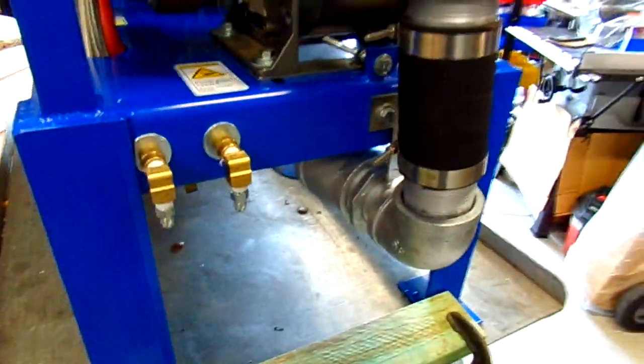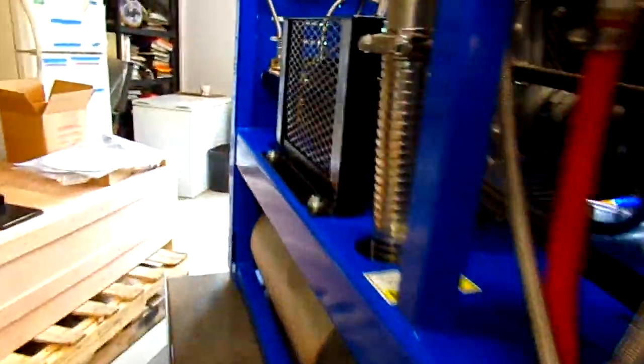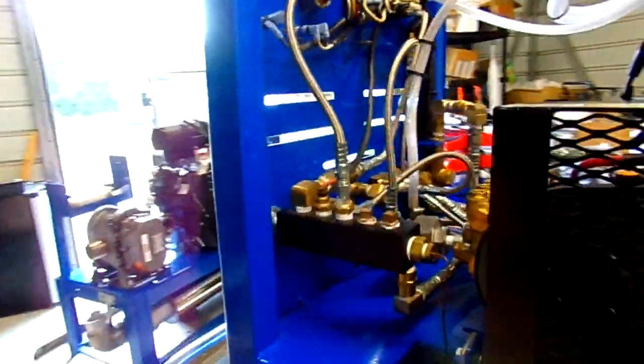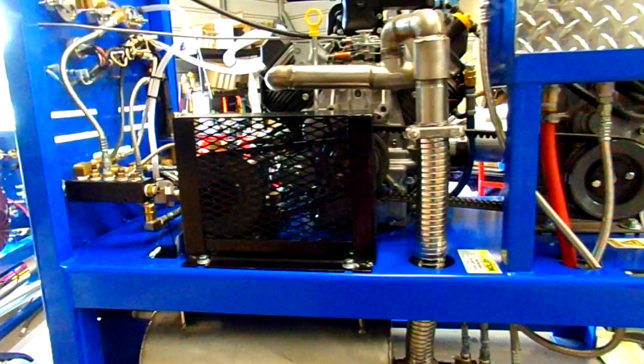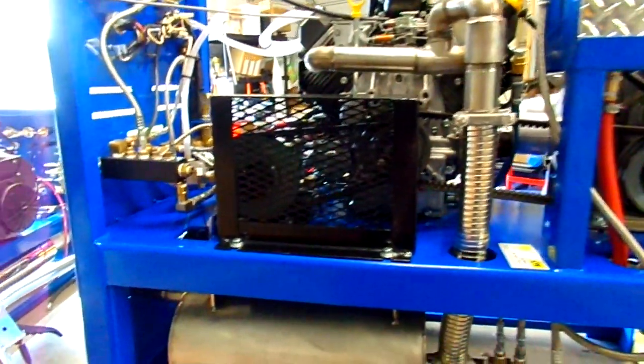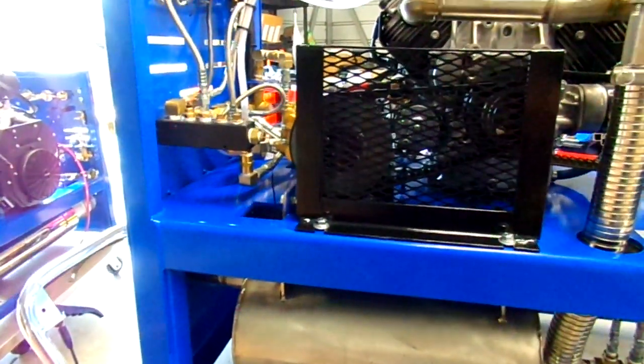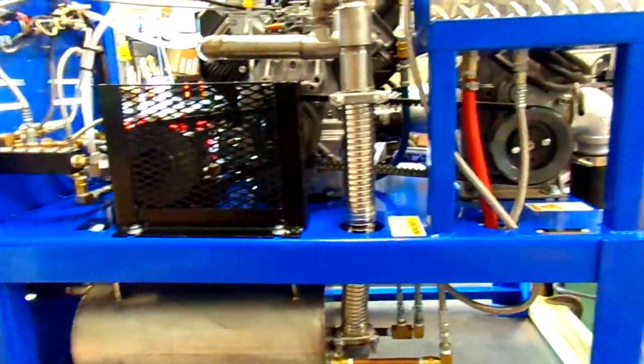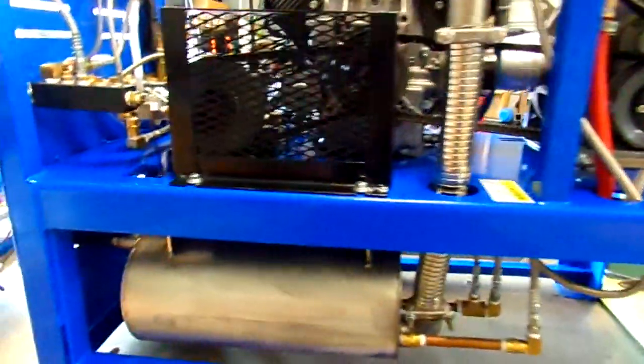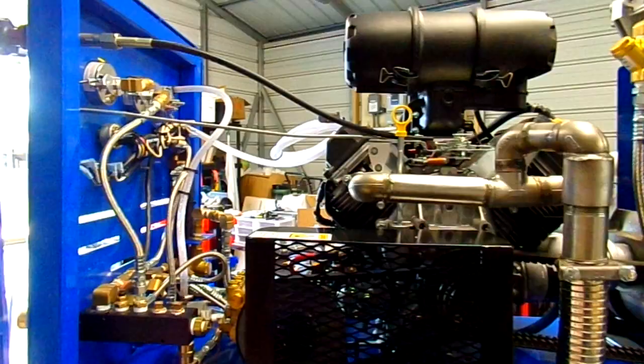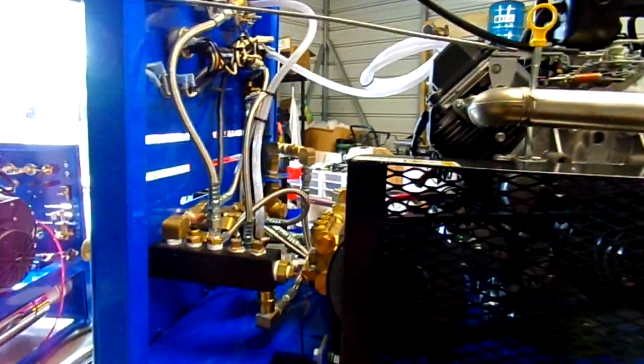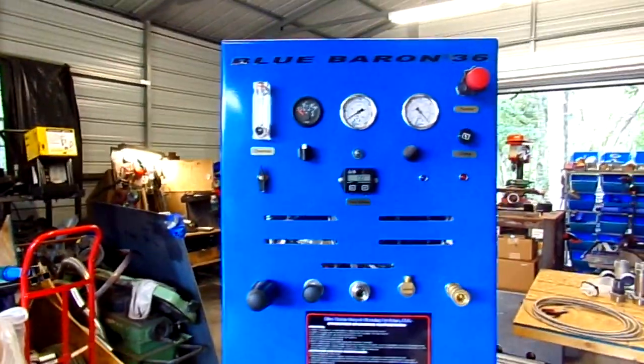And that's key, because you have to reach a certain sweet spot in the amount of dampening you get versus the amount of CFM that's allowed to go through. Too many obstacles, too many corridors, and too many partitions inside can really drastically affect your vacuum. Your CFM will be dragged down, and it can also cause your blower to overheat.